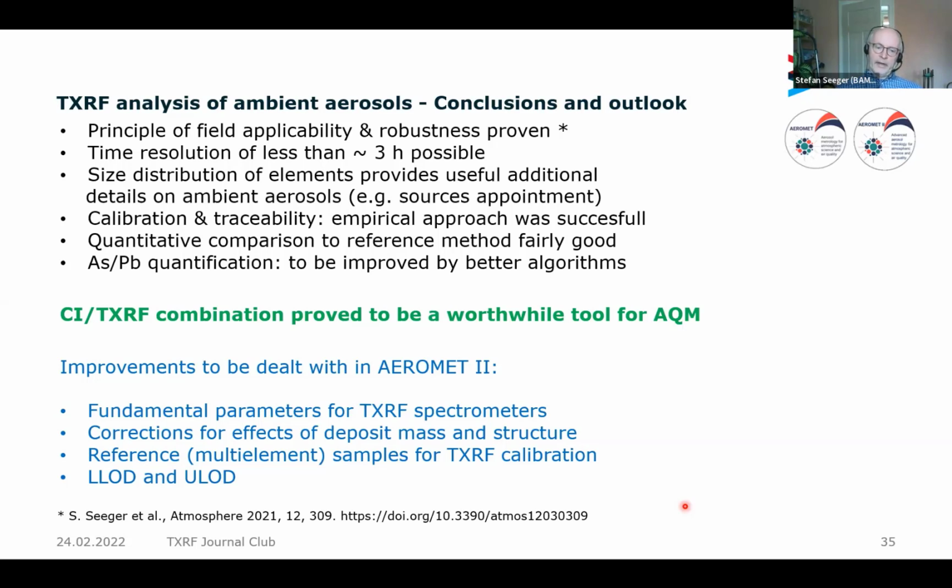You may imagine that the particles which are deposited do not form layers or very regular structures. The deposition pattern is regular, but in each of the dots where the particles pile up, there will be a very irregular structure, and this has consequences for the TXRF quantification. So that is something which we have to think about, and I pointed out already the importance of calibration.